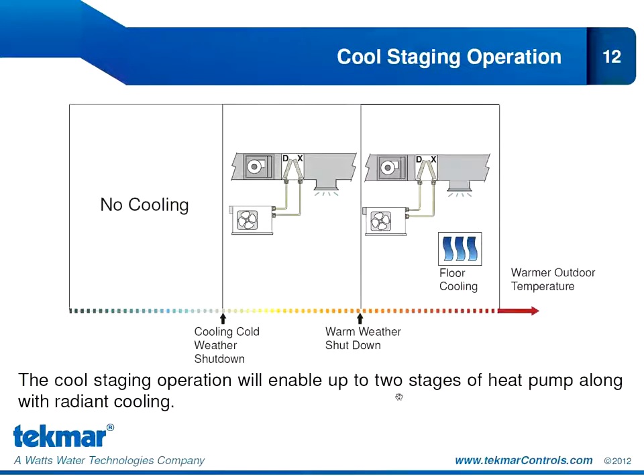Our cooling staging operation shows a similar chart to the one we just saw, except now we're starting off with cold outdoor temperatures and gradually getting warmer until we're at warm outdoor temperatures shown in red. When it's cold outside, we have no need for cooling equipment, so we're not going to stage any of it on. As the outdoor temperature rises above our cooling cold weather shutdown, we can now bring on stage 1 and stage 2 of our heat pump for cooling.